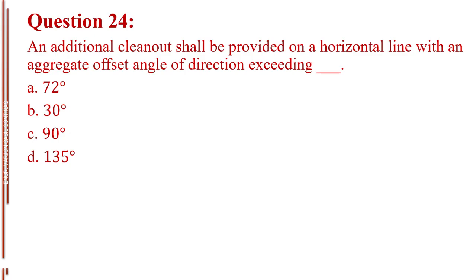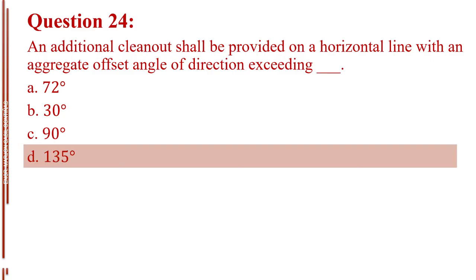Question number 24. An additional cleanout shall be provided on a horizontal line with an aggregate offset angle of direction exceeding blank. Letter A, 72 degrees. Letter B, 30 degrees. Letter C, 90 degrees. Letter D, 135 degrees. The answer is Letter D, 135 degrees.